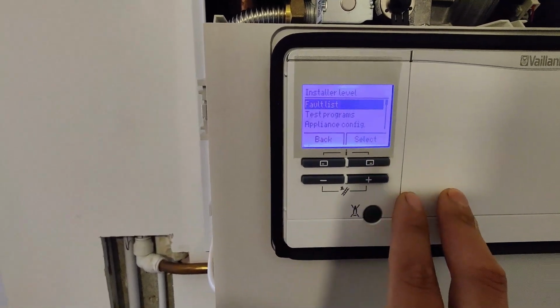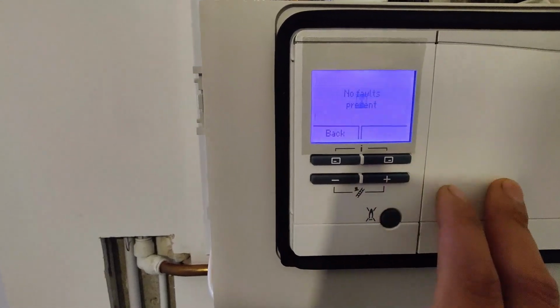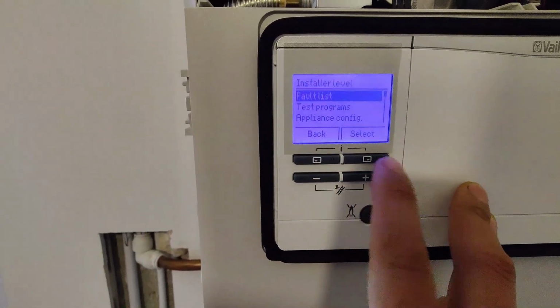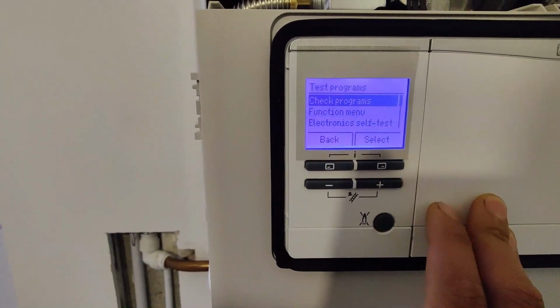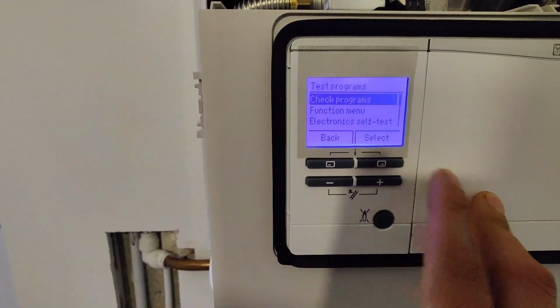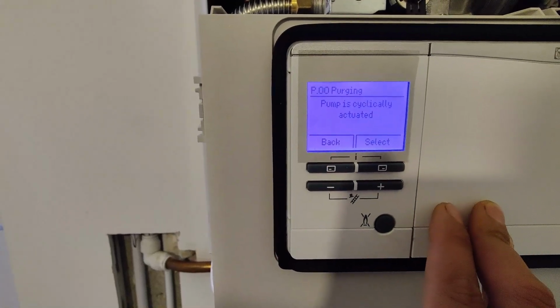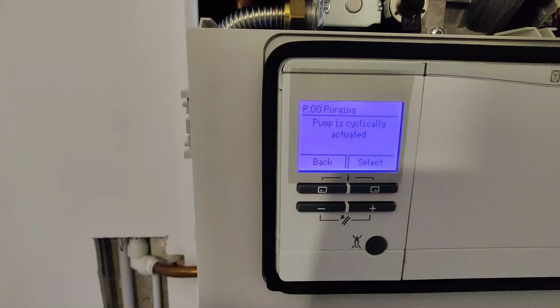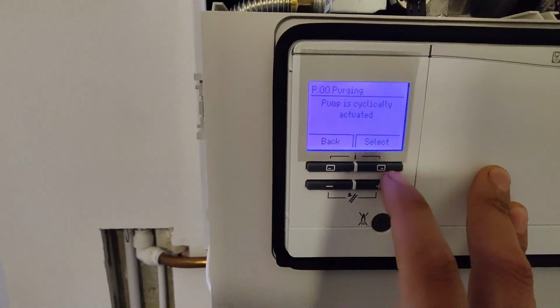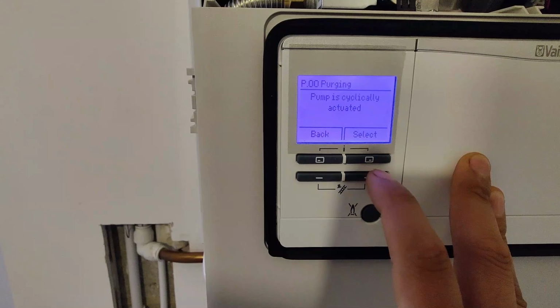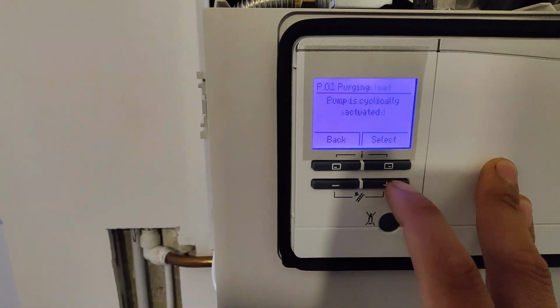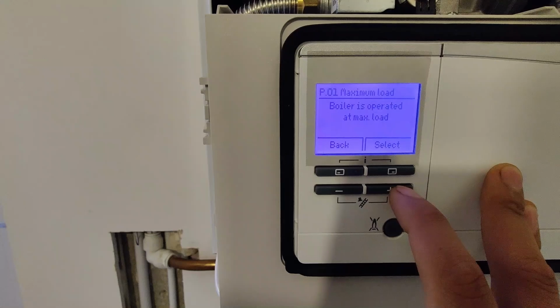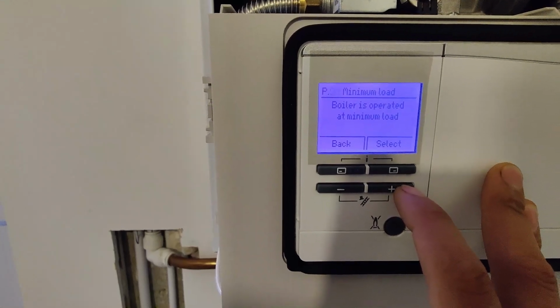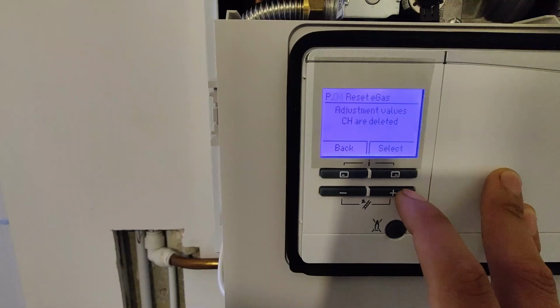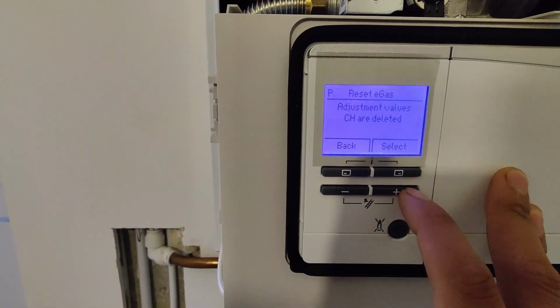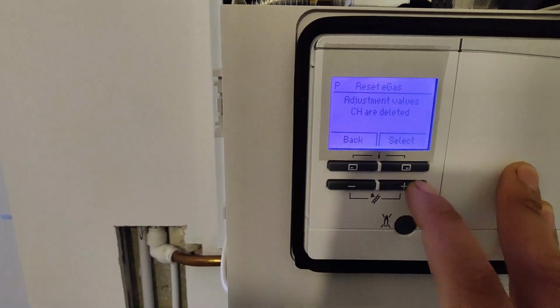Okay, so we go into the installer level. Let's have a quick look to see if there are any faults on it. So no faults present. We go to test programs. We can check programs. So if you go in there, we can do our P01, P00 and P02. So P00 is pump kind of purging mode. So the pump's just cycling one way or the other. P01 will be maximum load. P02 is minimum load.